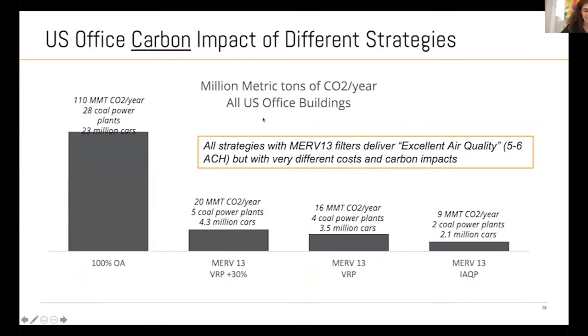So here I calculated for all the US offices, small, medium, and large, if all of them decided to choose a different strategy, what would be the impact on the climate? For example, if all of them have 100% outside air, it's equivalent to adding 28 coal power plants per year, imagine. And it's equivalent to adding 23 million passenger cars. The whole spiel here is that we don't have to compromise on our budget. We don't have to compromise our carbon impact. We can do this using the basic strategies of outside air, or only particulate filtration with a fan and a filter, or add portable air cleaning in the room, and achieve a very good air exchange rate at affordable cost.